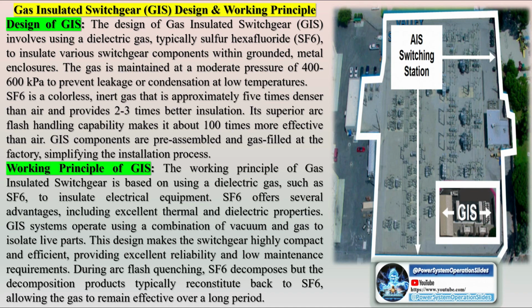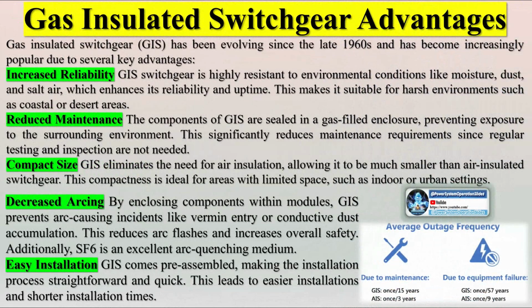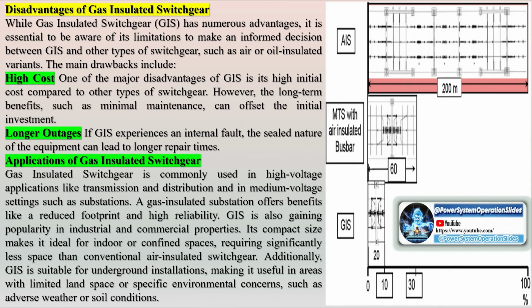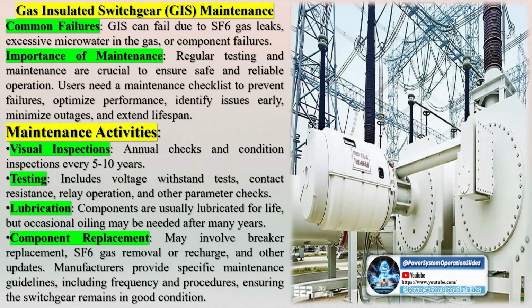Our focus here is on gas-insulated switchgear. Gas-insulated switchgear is a type of electrical switchgear where most components are enclosed in gas-filled chambers. The primary gas used in GIS is sulfur hexafluoride, SF6, which provides superior electrical insulation and arc quenching properties compared to air. This allows GIS to have a significantly smaller size and weight, making it ideal for confined, indoor spaces where high voltages are needed.